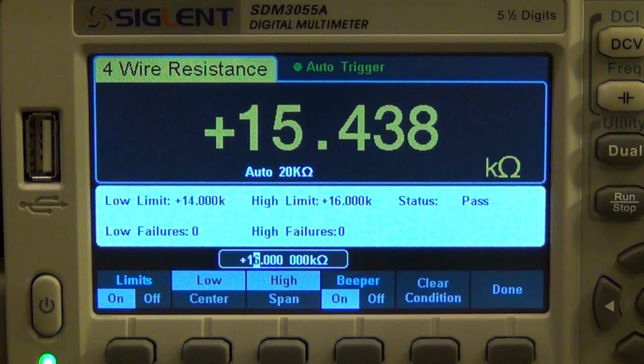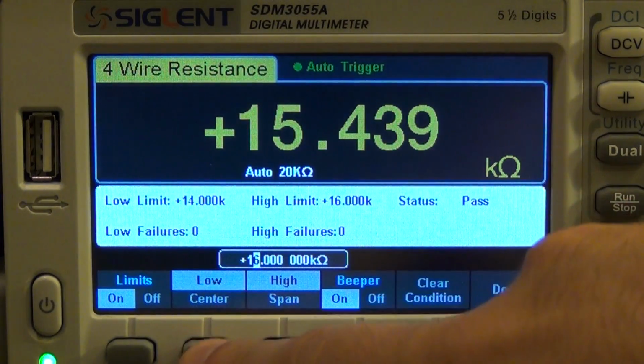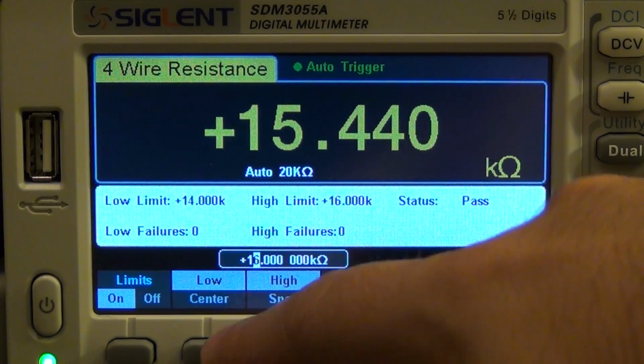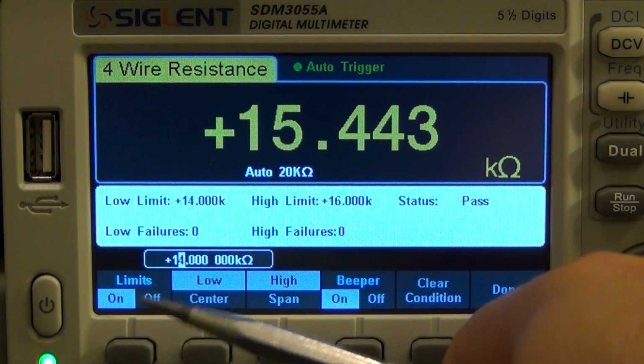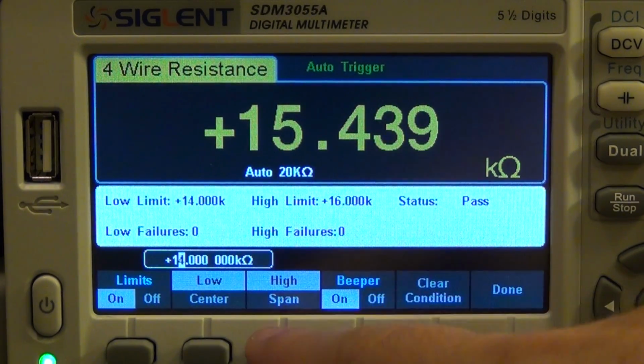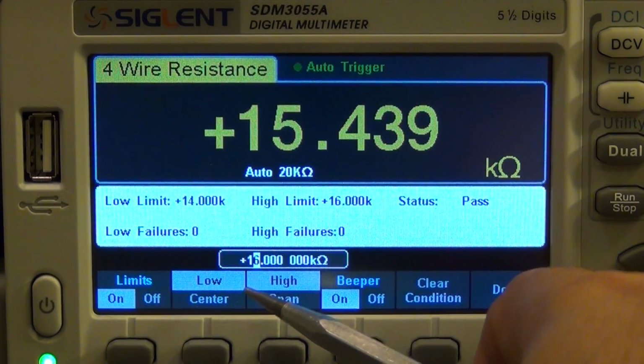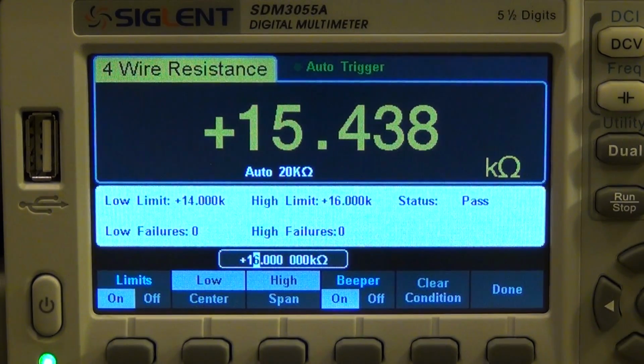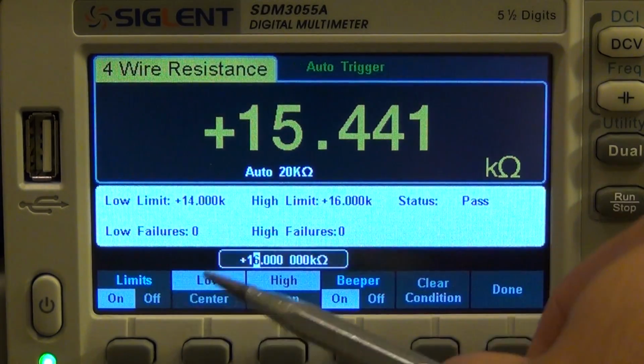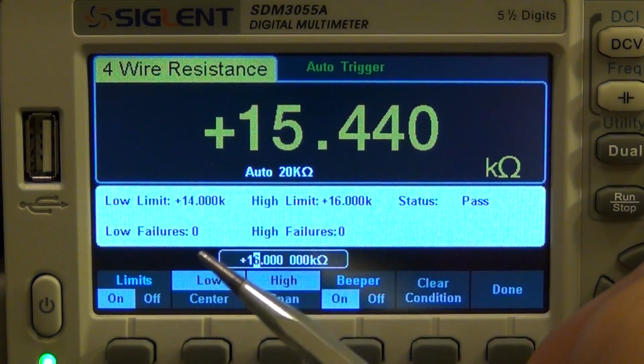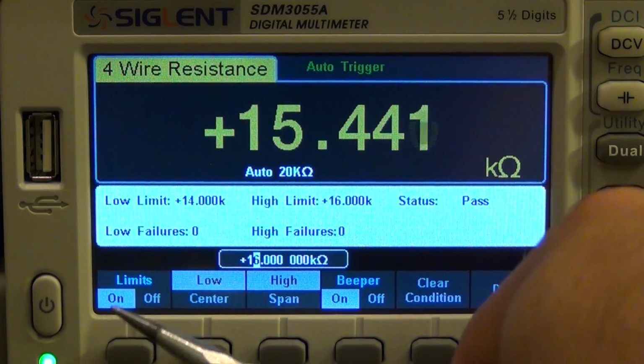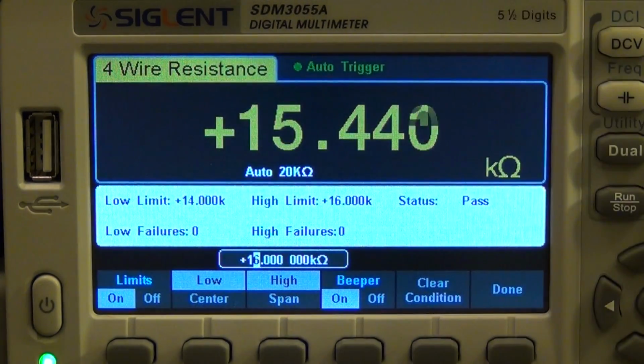Under the limits menu, we can set a limit of measurement, and that can be done in any measurement setting. Here I'm doing it in ohms, of course. Now I can set what the low value and the high value is, or the center and the span. So the low value I've set to 14 kilo ohm here, and the high value I've set to 16 kilo ohm. So any value between those two will be considered a pass. So you can see it will here tell me the status is right now in pass. The low limit and high limit are all displayed, and it has no low failures and no high failures.